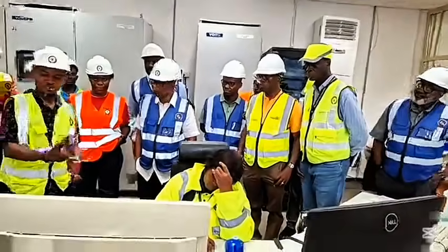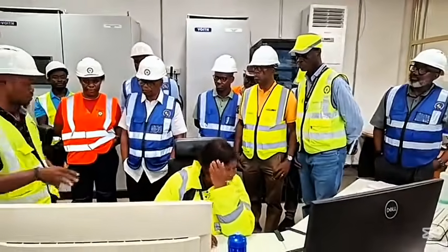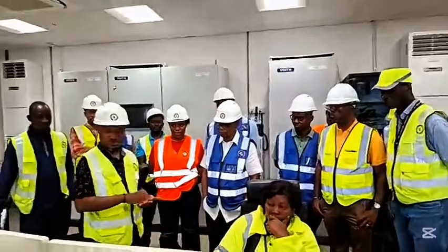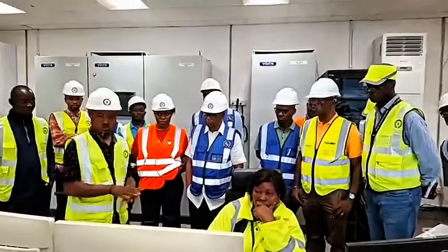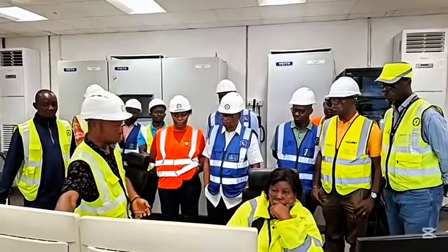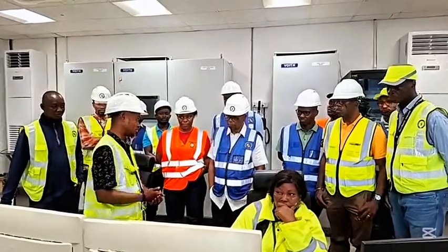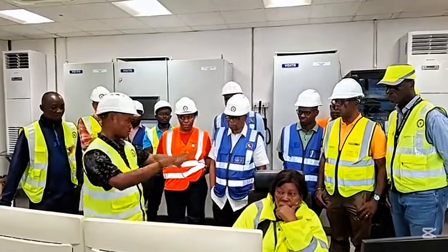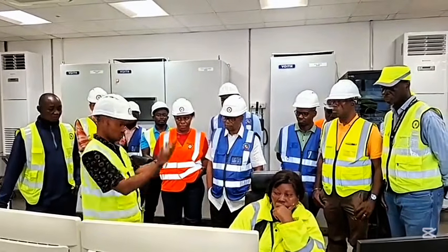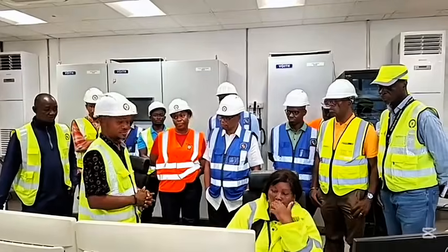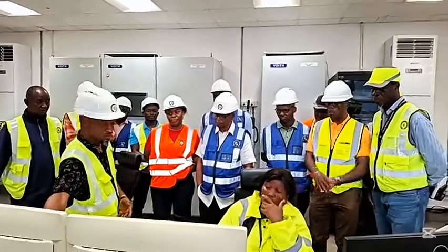Probably there was some maintenance work done, and the maintenance team wants to do some inspection. You don't want the unit synchronized at that station. So they give the first command at low load while the top is spinning, then they do all the unit inspection. Once they check and are satisfied, then we can take the unit to synchronize.